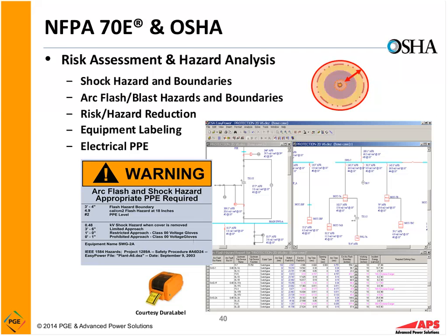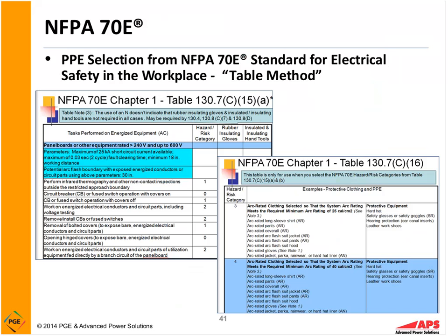You can put labeling up, and so you can come up with a shock hazard and the arc flash hazard boundaries, the risk hazard reduction strategies, equipment labeling, electrical PPE requirements. So these are all parts of a risk assessment and hazard analysis as discussed in OSHA and NFPA 70E.